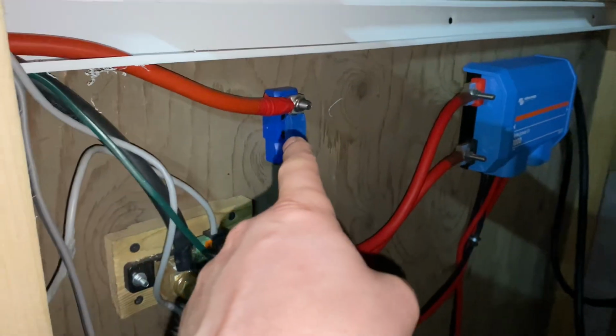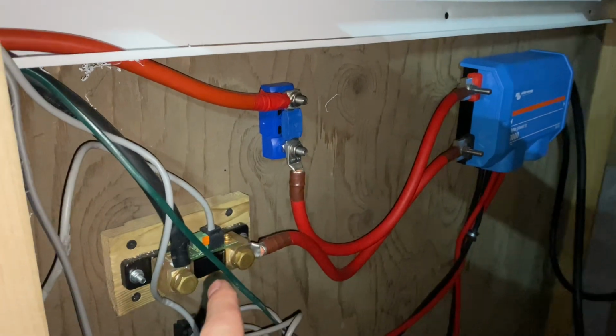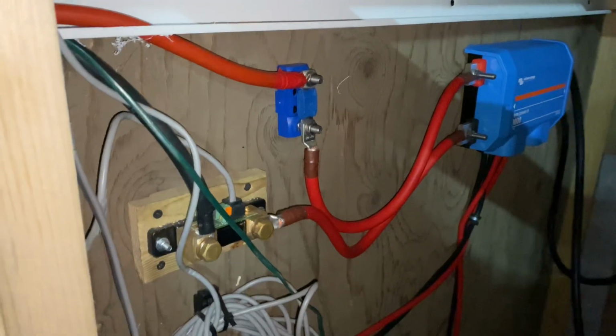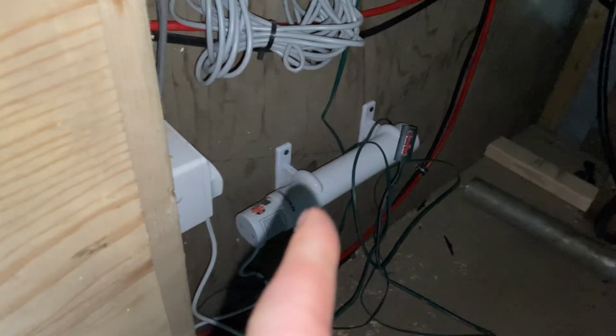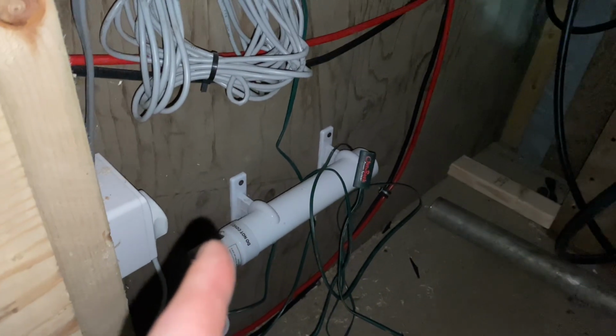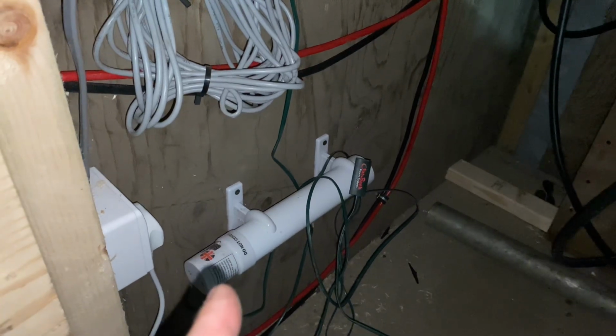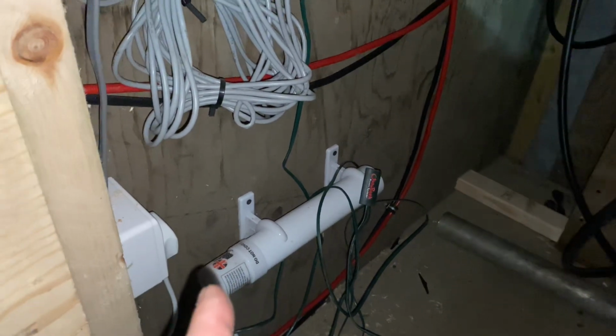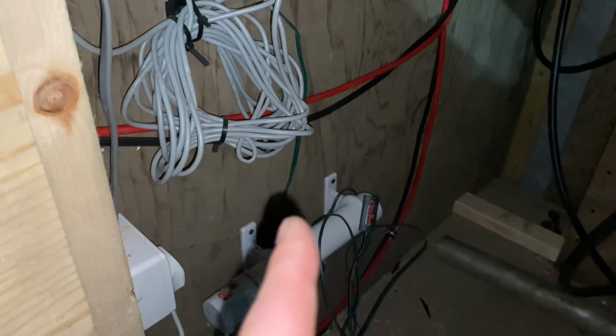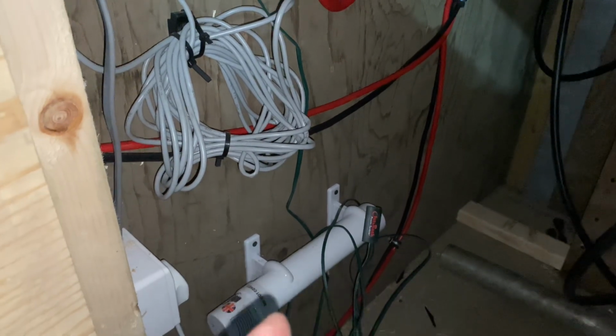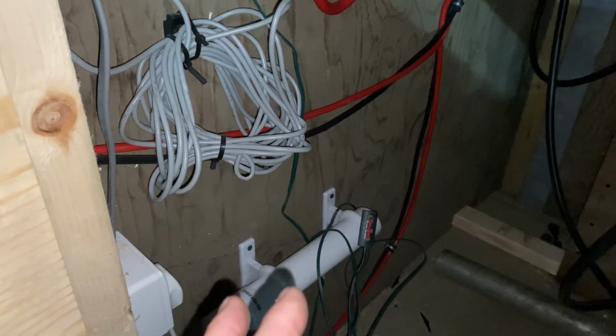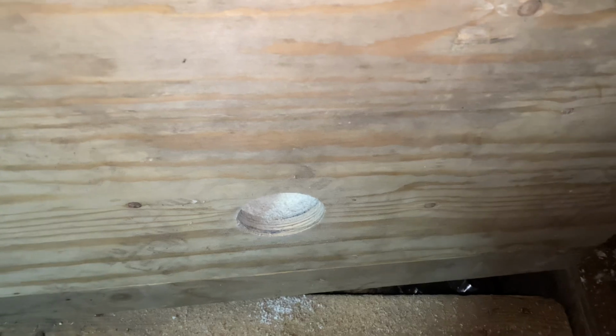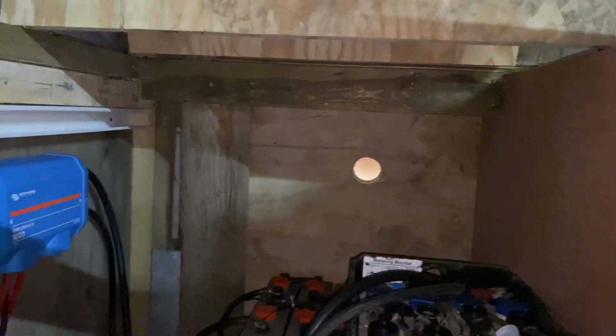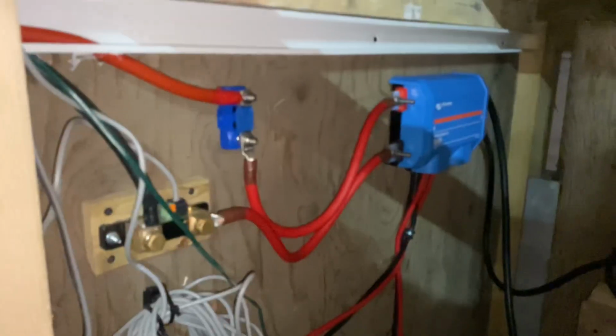We then come into the battery cupboard. We've got a 200 amp fuse there, and we've got a battery shunt. I've got to run a cable to that to work. We've then got a 30 watt greenhouse bathroom heater. We'll have that turned on in the winter if we need it, just to keep the batteries up to temperature, because batteries don't charge below 5 degrees, so we just need to keep this above 5 degrees. It's a problem that we've got to have it ventilated, so we've got a vent coming in at the bottom of the door there, and a vent going out up there for any hydrogen gases.